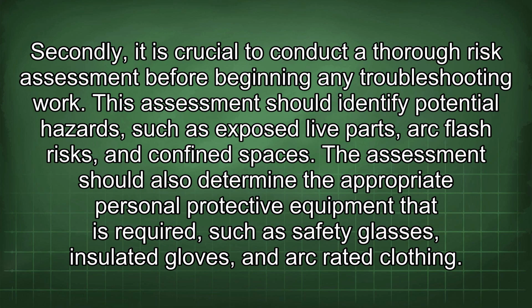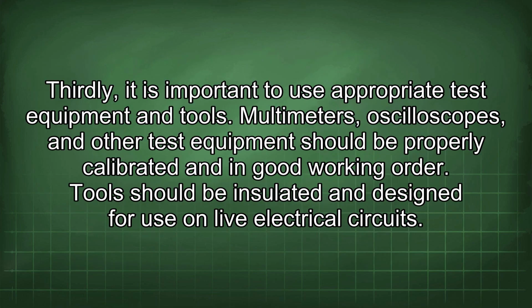This assessment should identify potential hazards such as exposed live parts, arc flash risks, and confined spaces. The assessment should also determine the appropriate personal protective equipment that is required, such as safety glasses, insulated gloves, and arc-rated clothing. Thirdly, it is important to use appropriate test equipment and tools. Multimeters, oscilloscopes, and other test equipment should be properly calibrated and in good working order. Tools should be insulated and designed for use on live electrical circuits.